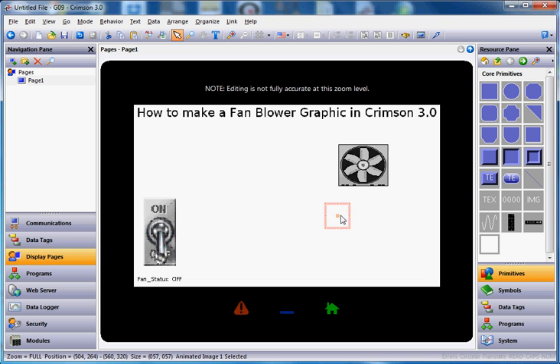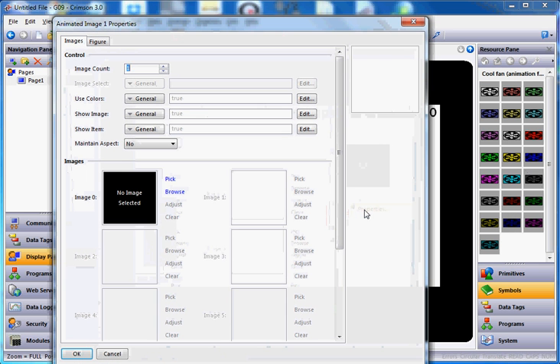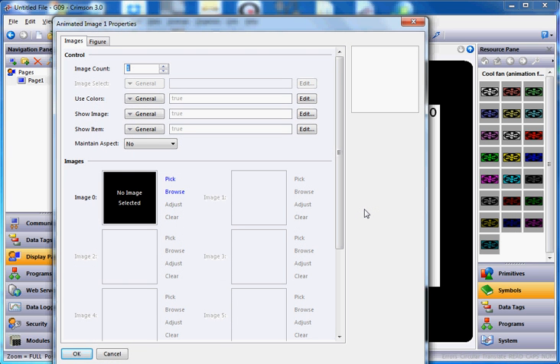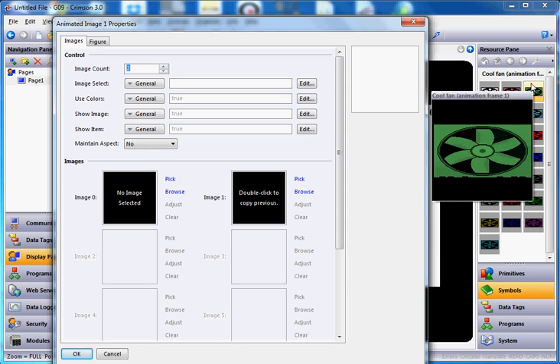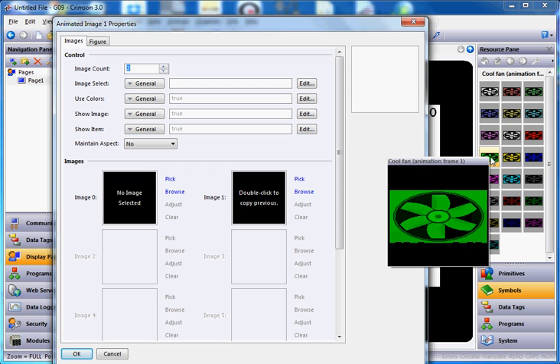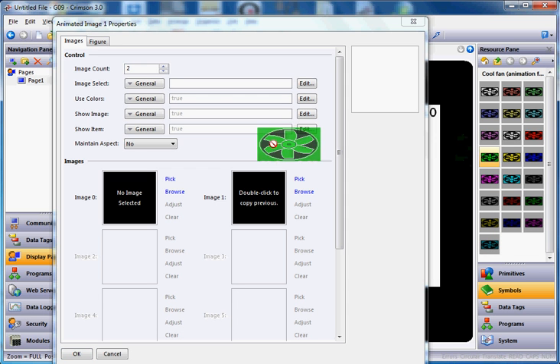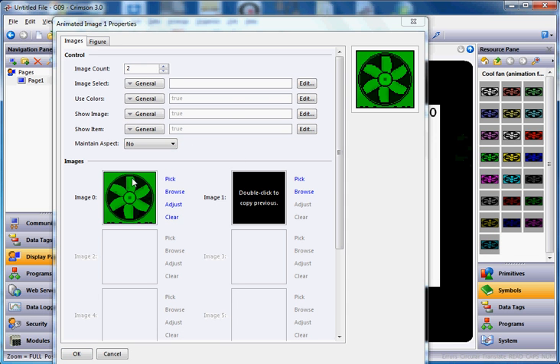I'll right-click on that and go to properties. We're going to need to use two different pictures of a fan and oscillate between them to make it look like the fan is blowing. So up here where it says image count one, change that to two so we get two images. Notice that Crimson went from primitives back into symbol factory and brought us right back to cool fan animation frame one. I'm going to use the green one here — I'll drag it over and drop it right here. That's the first picture.